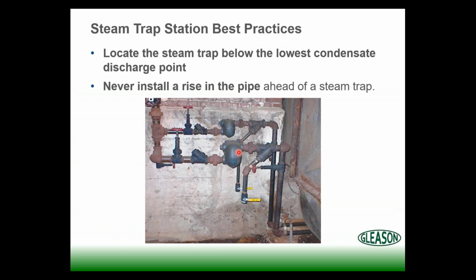We also want to always locate the steam traps below the lowest part of what we're trapping. For example, you can see in this coil application, steam traps are a liquid level device, and they will maintain a liquid level wherever the orifice is in that steam trap. So in this case, maybe the bottom quarter or the bottom third of these coils are staying submerged. So we always want to locate it below the lowest part of what we're trapping, and also never install a rise in the pipe ahead of the steam trap. So again, just some things to keep in mind.